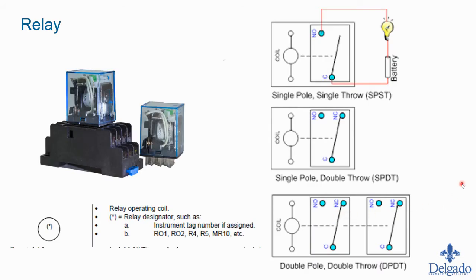Relays are typically what we call an interposing device. What happens is the PLC output will energize the relay coil, and when we energize the relay coil, it'll actually change contact states. A relay is basically a switch that we can control automatically. You can see here it says DC 24 volts — that's the coil wire. When we put 24 volt DC on this coil, it turns into an electromagnet.